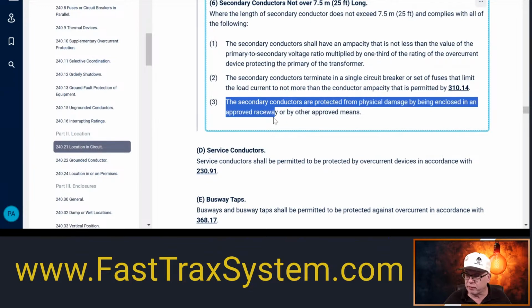And then lastly, it says the secondary conductors are protected from physical damage by being enclosed in an approved raceway. Approved means whatever your AHJ is happy with, whatever they think the approval is okay with, it still has to be a raceway. And raceways are things like rigid, intermediate, conduit, EMT, PVC. All these things are raceways. MC cable is not a raceway. It may walk like a duck, quack like a duck, but it's not a raceway.